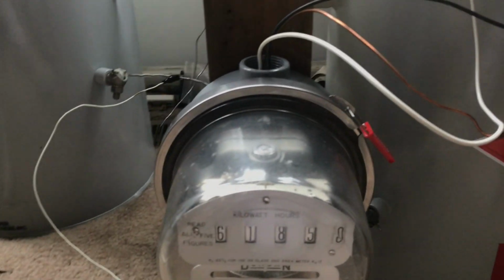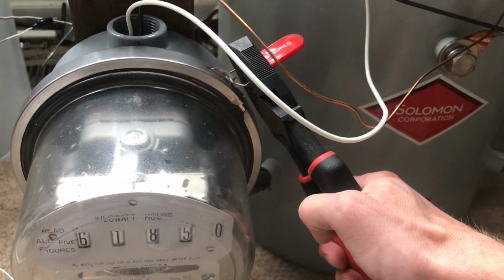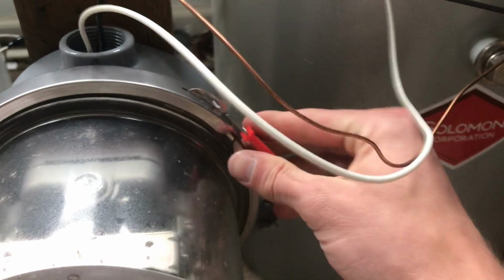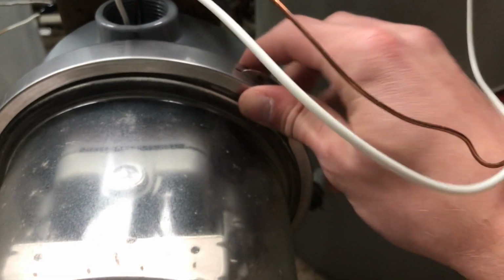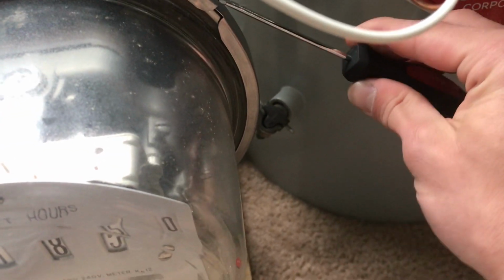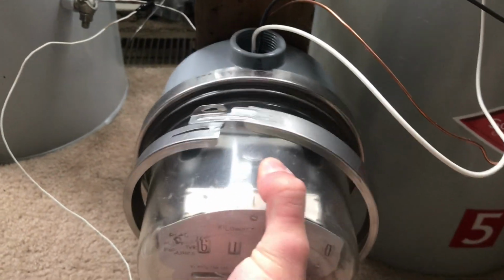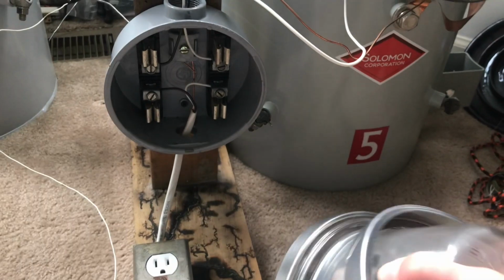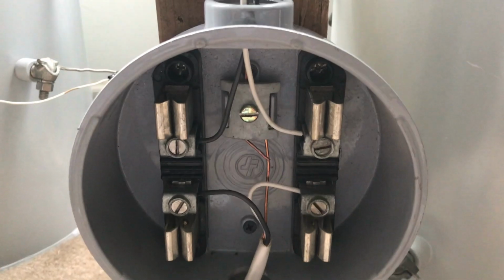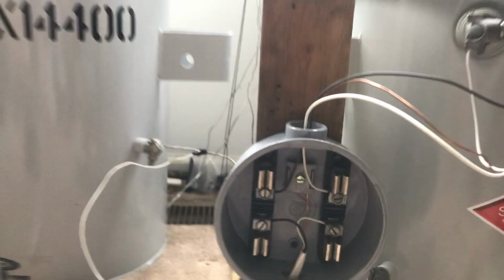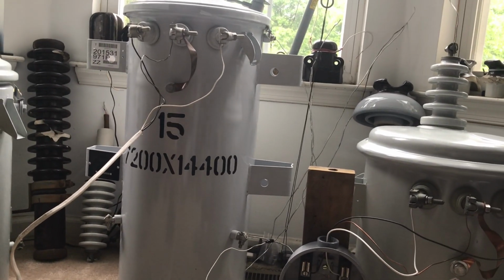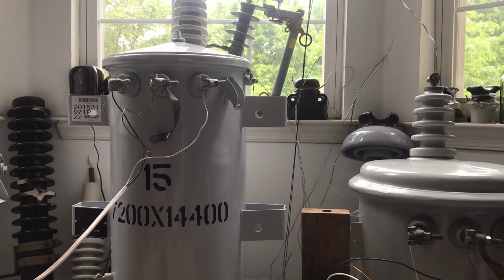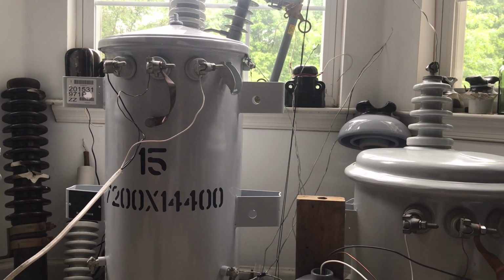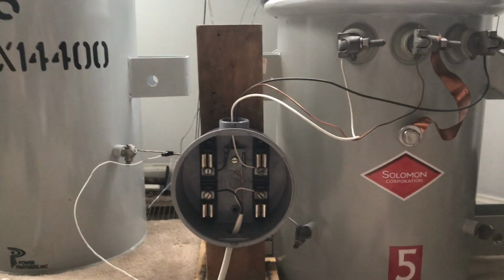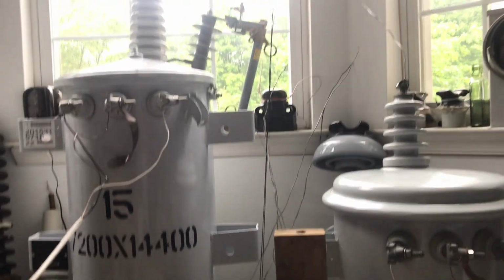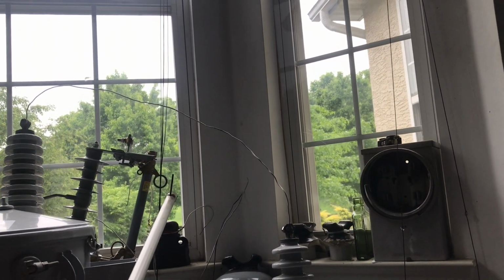So right now, I'm going to open this meter and show what is inside. And to get inside, you have to cut the utility seal. Once the locking ring is off, the meter can simply pull out of the socket. As you can see, now that the meter is out, I will energize the system and stay away because I personally don't like to be near 7,200 volts when it's live. But turning on, you can hear the transformers hum, and the socket there is now live. And just to do an arc to show that this is live at more than residential voltage.